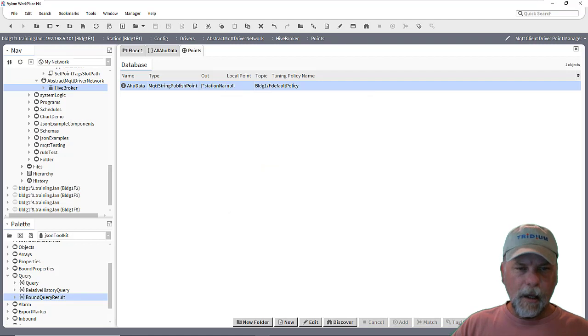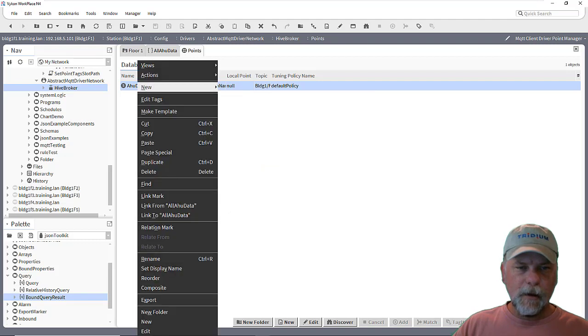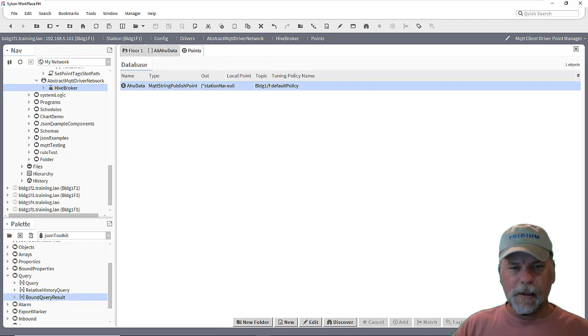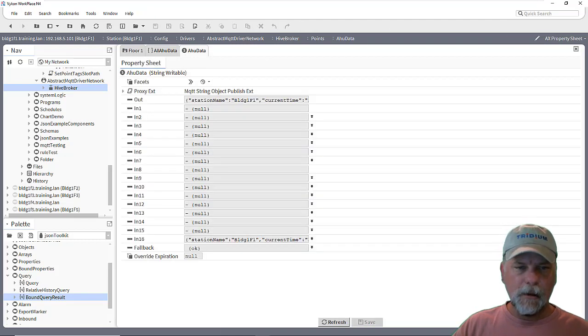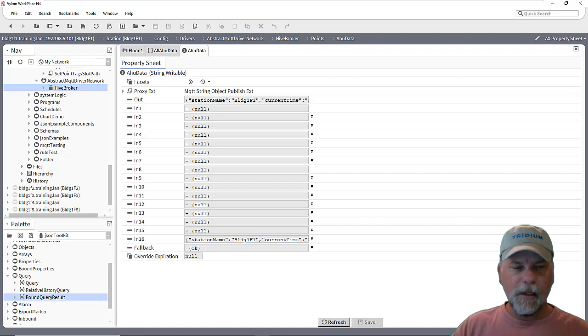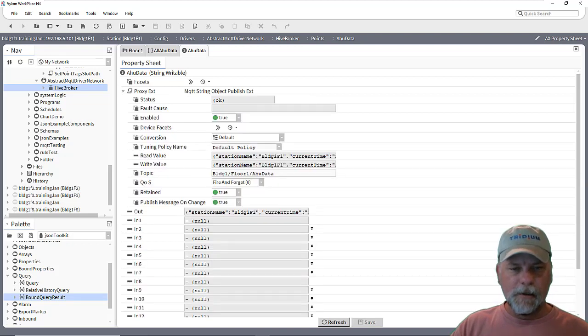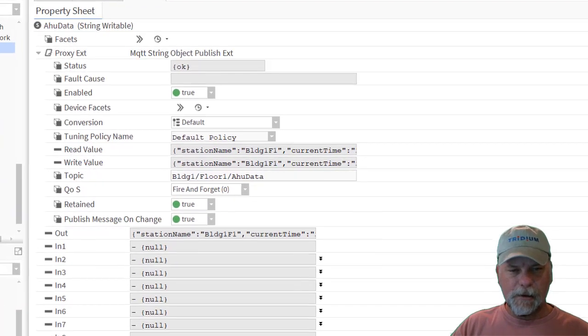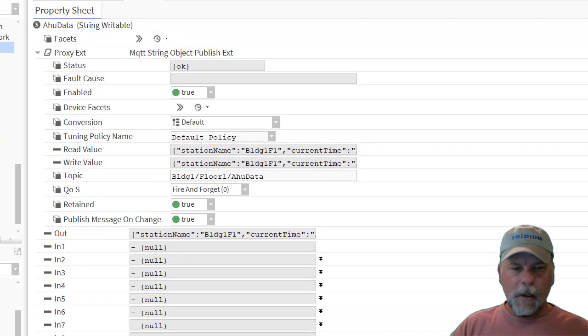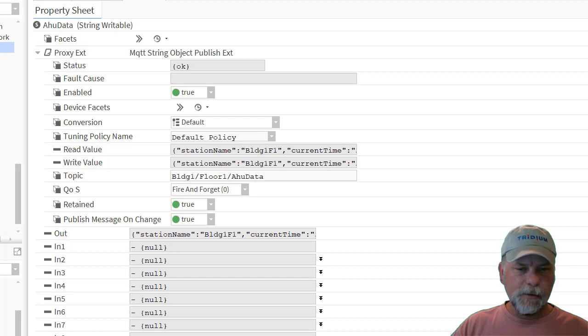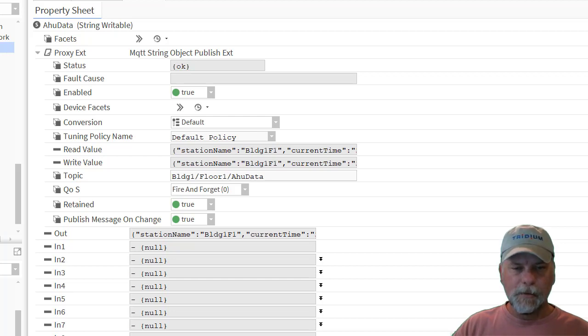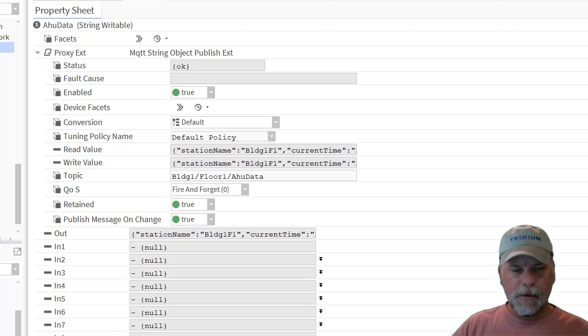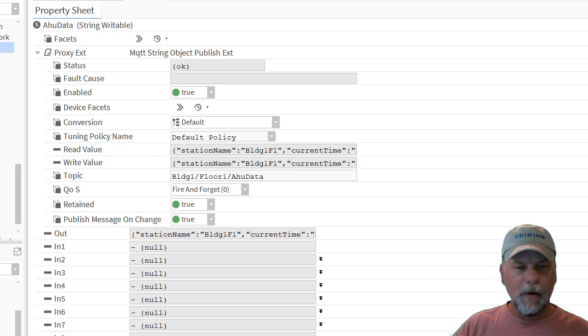And when you look at these MQTT proxy points and we look at the proxy extension, there's a few properties that you might want to consider editing. There's publish on change, which defaults to true and this retained property as well. And then there's a QoS here as well, which by default is set at fire and forget, which means the publisher is just going to send the message and assume it gets to where it's supposed to get to.